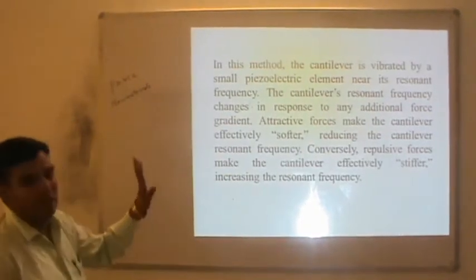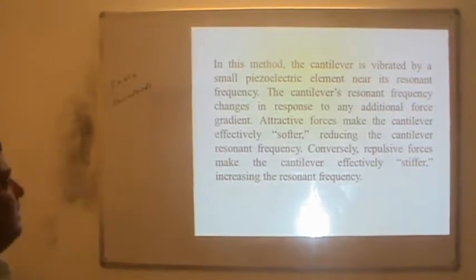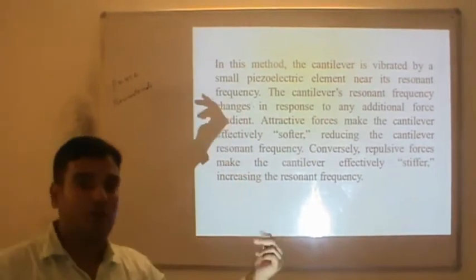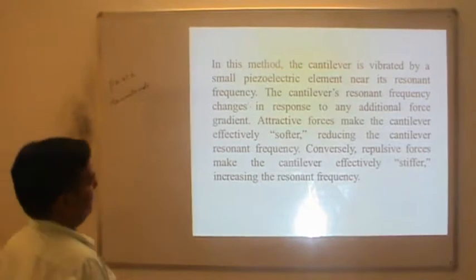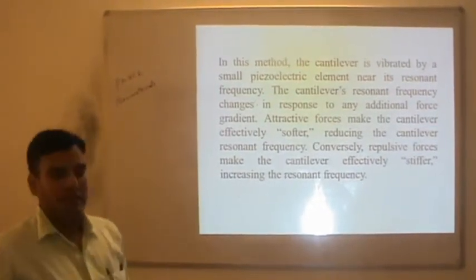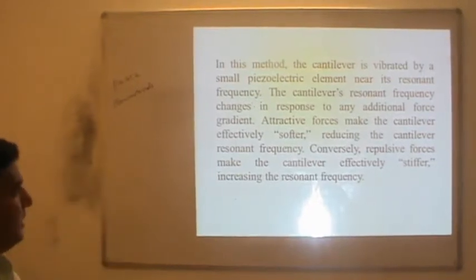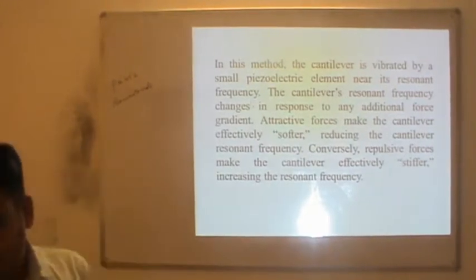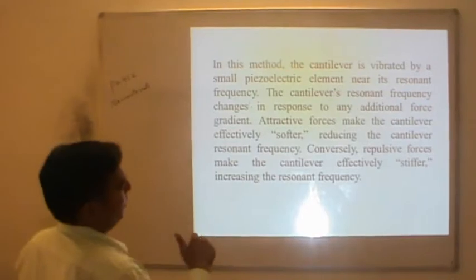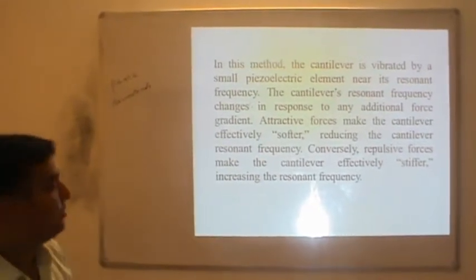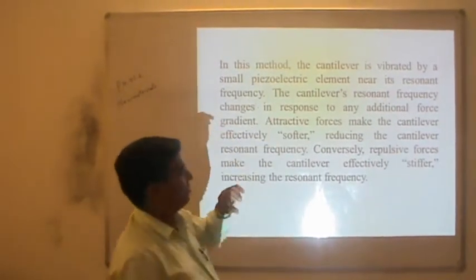In electric force microscopy, the cantilever is vibrated by a small piezoelectric element near its resonant frequency f₀. The cantilever's resonant frequency changes in response to any additional force gradient. If there is an attractive force, the cantilever effectively moves toward the sample — becoming softer — and the frequency decreases. If repelled, the cantilever stiffens and the frequency shifts to higher values.